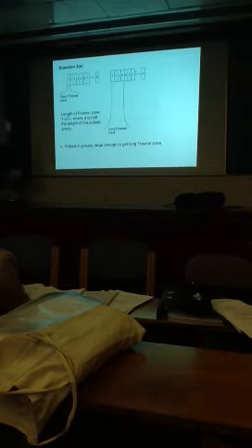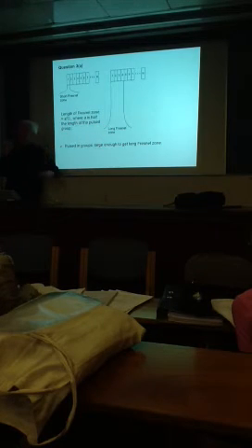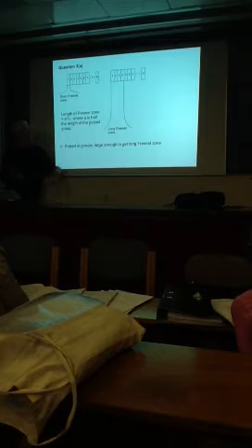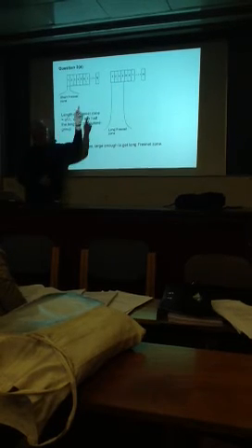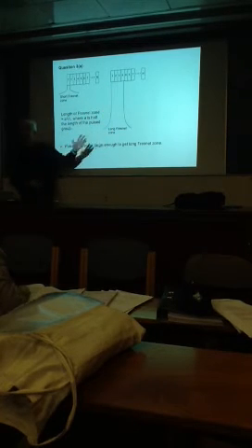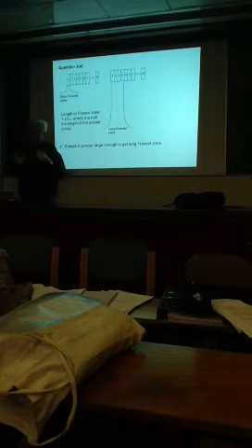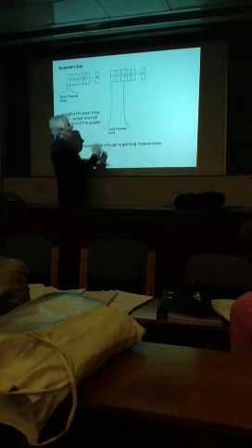So that doesn't work. Instead, what we need to do is pulse in groups. By pulsing a group of elements at exactly the same time, we're able to have a much larger effective radius of our transducer, therefore a much longer Fresnel zone, but at the same time still have a large number of lines. The number of lines is only slightly reduced by pulsing in groups.